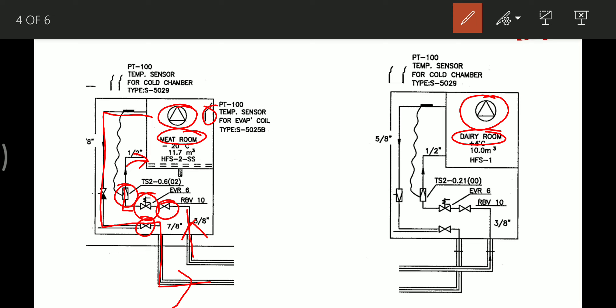In the dairy or veg room, the refrigerant also enters through manual valves, then through a thermostatically controlled solenoid valve, then the expansion valve, then the evaporator coils, and back to the system. The main difference between the two systems is that in the dairy room or veg room there is a constant pressure valve or back pressure valve, whereas in the meat room or fish room there is only a non-return valve. These back pressure valves are spring-loaded and maintain a constant pressure inside the evaporator.